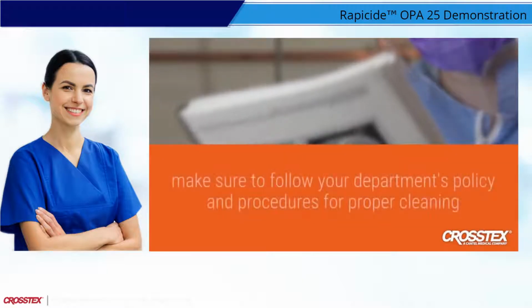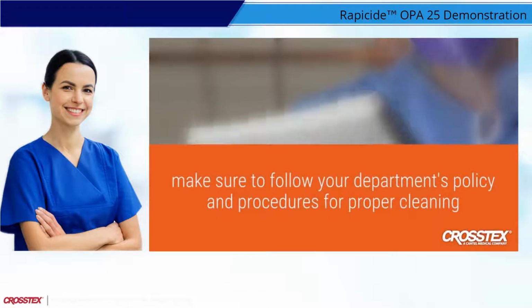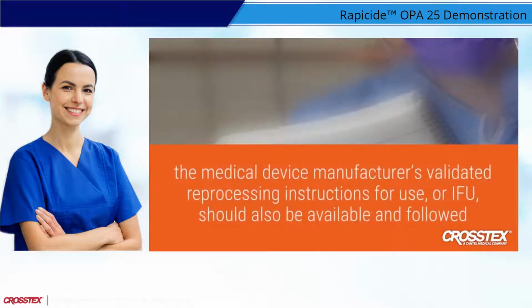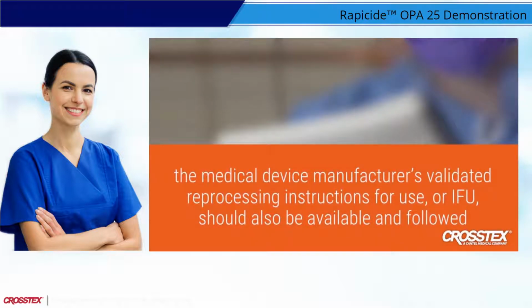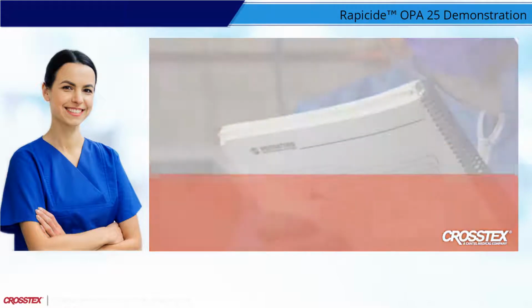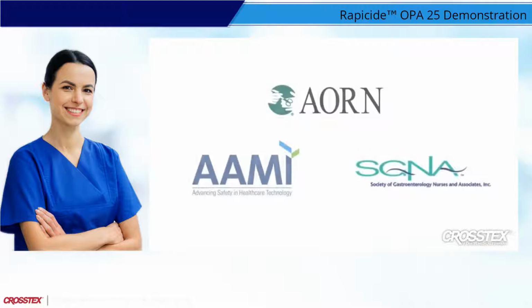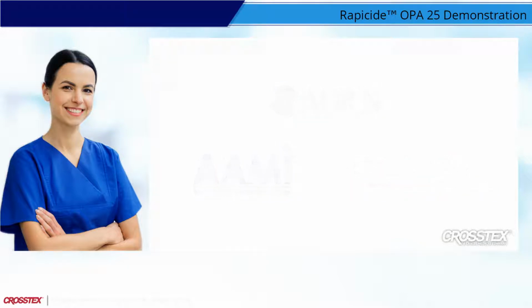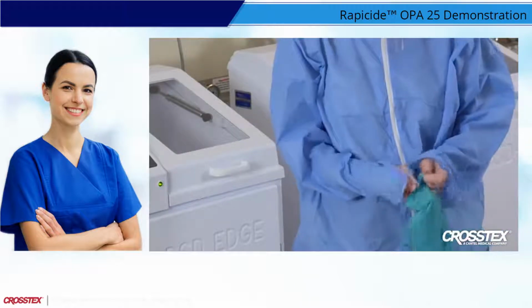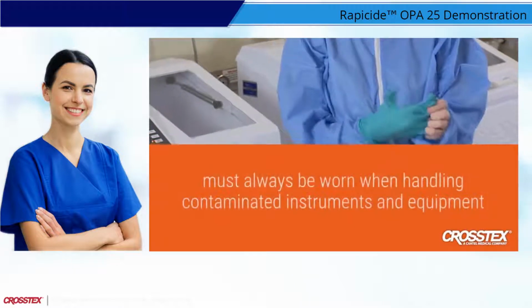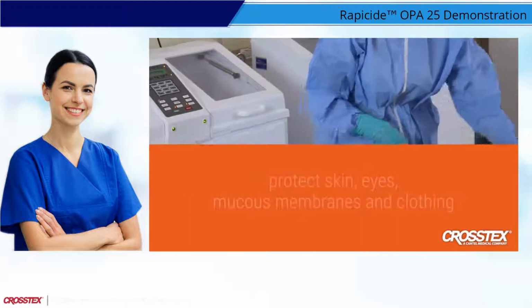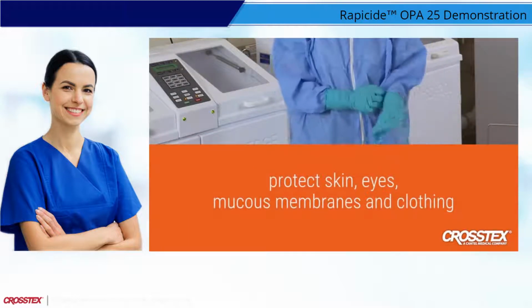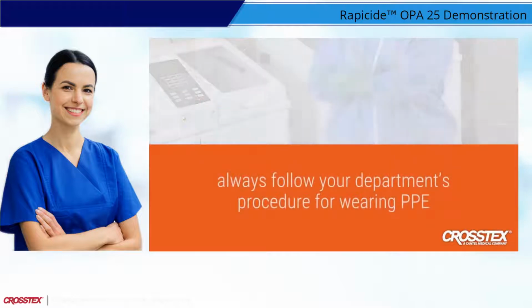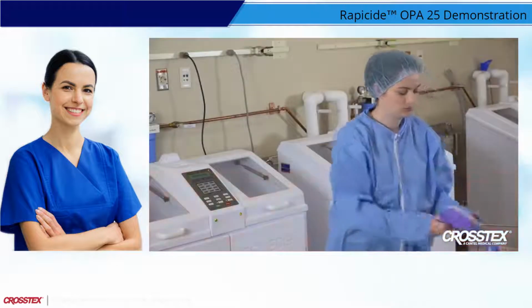Make sure to follow your department's policy and procedures for proper cleaning. The medical device manufacturer's validated reprocessing instructions for use, or IFU, should also be available and followed. General cleaning and decontamination guidelines are available from industry associations such as AORN, AAMI, and SGNA for additional information about cleaning standards and practices. Personal protective equipment, or PPE, must always be worn when handling contaminated instruments and equipment to protect skin, eyes, mucous membranes, and clothing from splashes. Always follow your department's procedure for wearing PPE when high-level disinfecting.